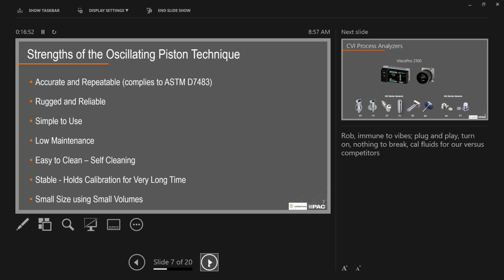About the simplicity, you install the sensor into the line, you power the electronics, and then you start reading viscosity. So it's really intended to be a plug-and-play system. Very low maintenance. Ideally, it's intended to be no maintenance, but certainly there are some companies that have preventative maintenance plans that mandate that the sensors be cleaned every 3 months, every 6 months, every year. So it's very simple to remove the sensor. The 311 sensor, which is common in printing applications, just has a toolless clamp that holds the sensor in place. So there's a thumb screw. You can unscrew that, remove the clamp, pop the sensor right out, clean it, and put it back in. And that's going to take no more than 5 minutes at most.